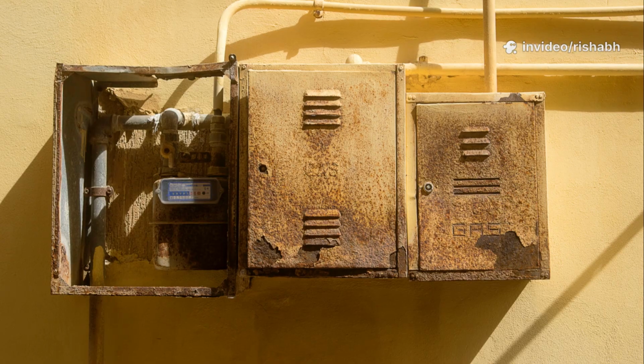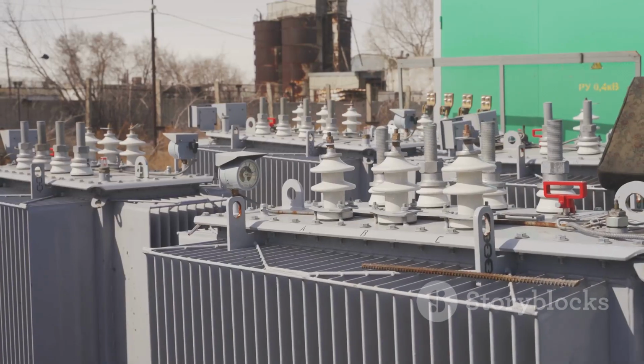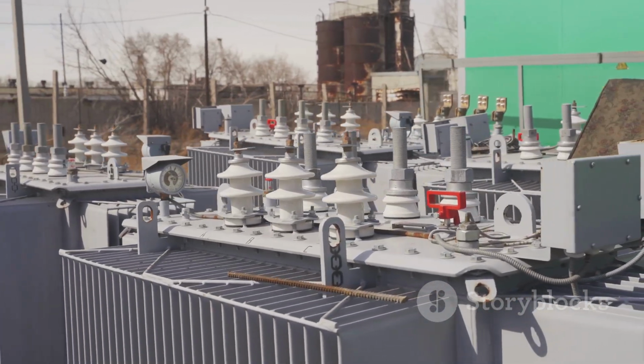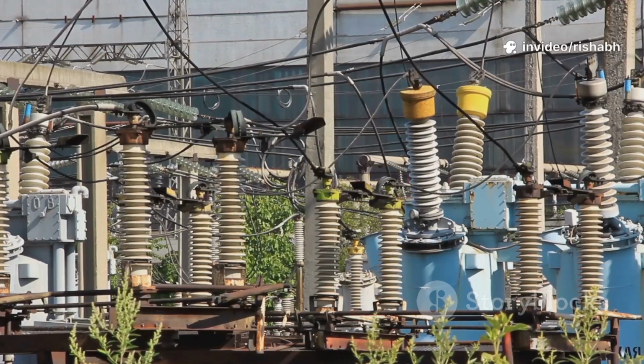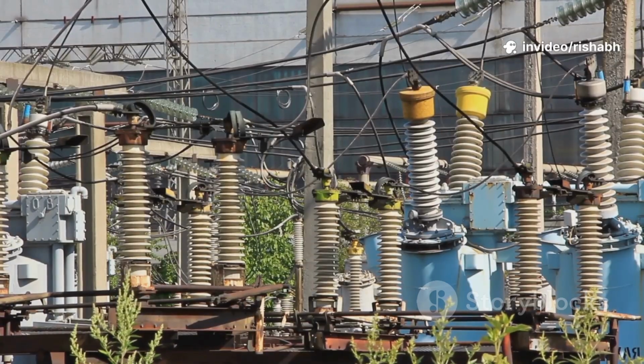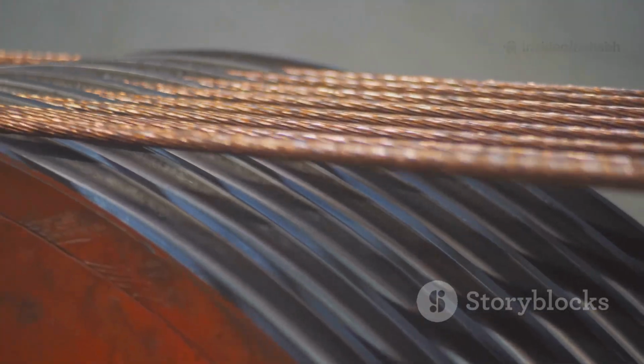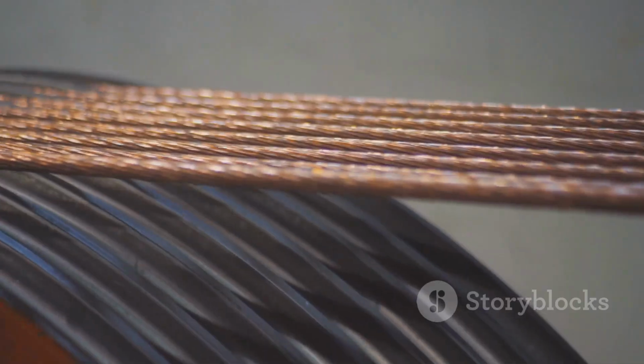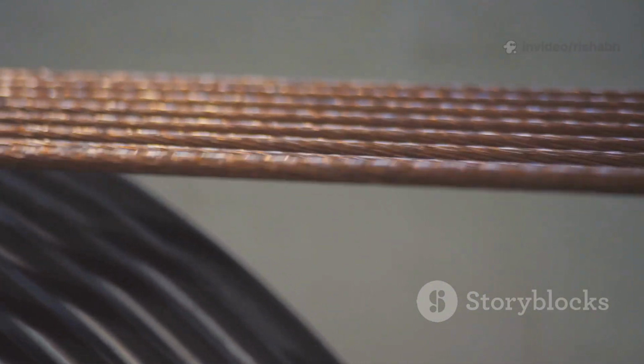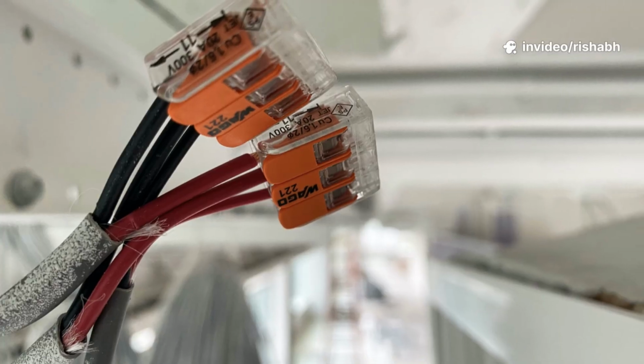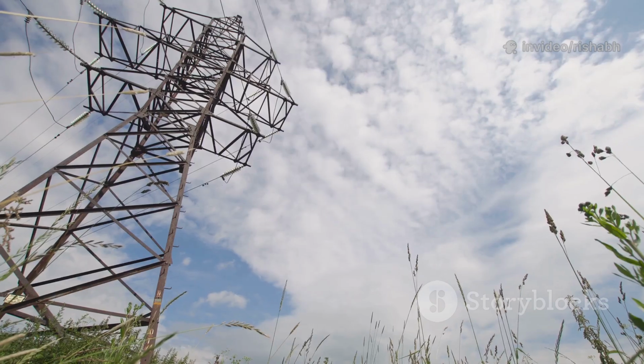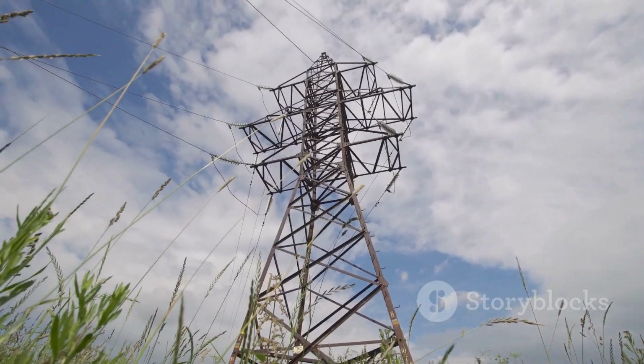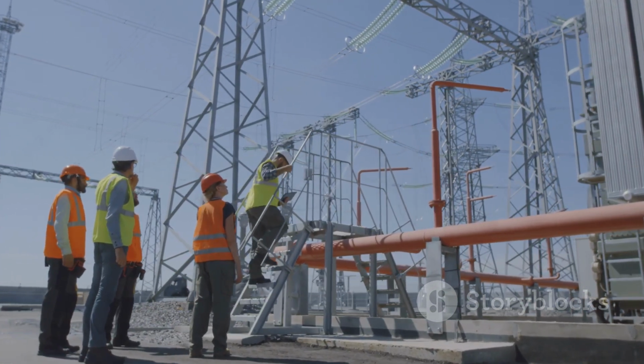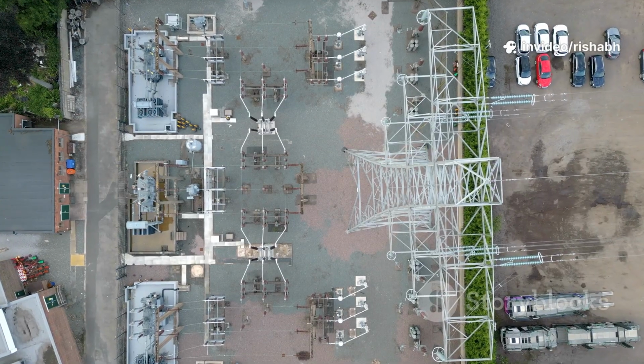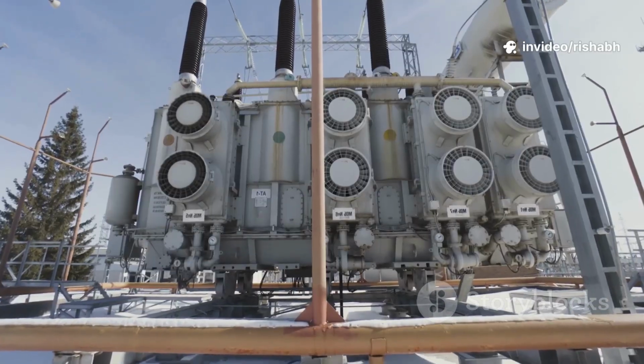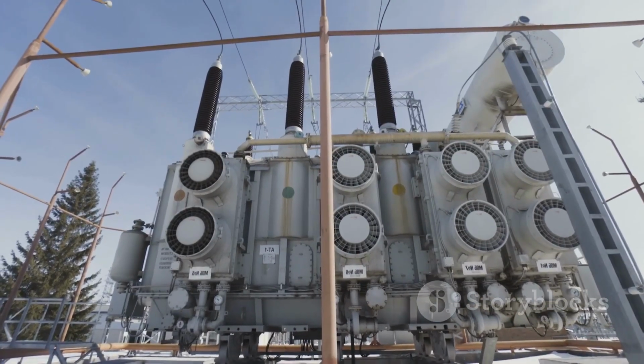Bushings are mounted onto the transformer tank cover or sidewall. The high-voltage bushings are typically large and mounted on the top cover, while the low-voltage bushings, carrying higher current but at a lower voltage, might be side-mounted. The connection at the bottom of the bushing, inside the transformer, is made via a flexible lead to the winding. The top of the bushing has a terminal for connecting to the external bus bars or transmission lines. These components are among the most critical in a substation. A bushing failure can be explosive and lead to prolonged outages, so their design, manufacture, and maintenance are of the utmost importance.